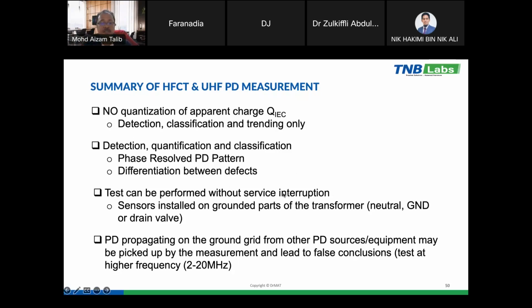But the challenge is that sometimes the PD propagating from nearby equipment can also be picked up by the measuring instrument. So it is difficult for us to differentiate whether the PD is coming from the actual equipment that we test, or from other equipment nearby the test object. So we need a more advanced filtering system to eliminate the noise or the signal coming from the other equipment.